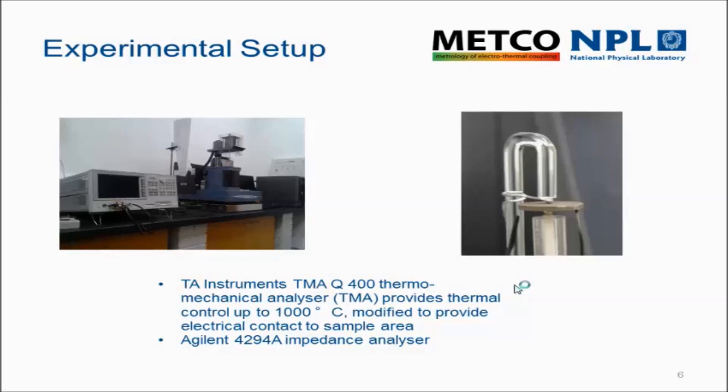We have a couple of systems we can use for doing resonant measurements, but the one we're using for the results I'm presenting today is based on a thermomechanical analyser — a commercial system for high temperature analysis that can work up to 1000°C. We've modified this to place some small electrical contacts and electrical wiring to enable us to carry out resonance measurements. The other part of the equipment is an impedance analyser.